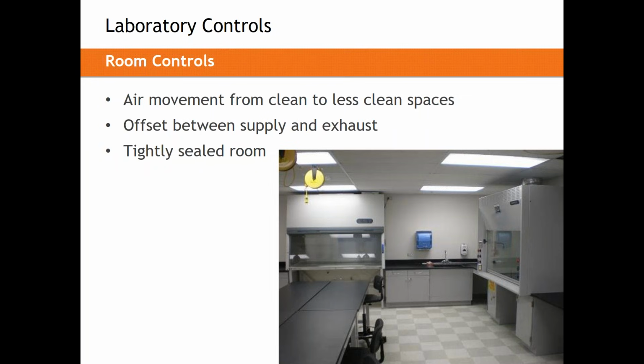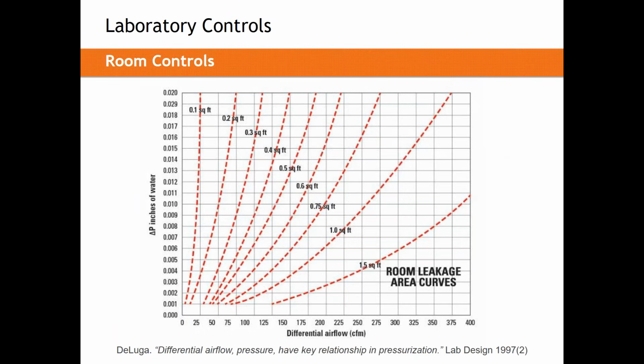And I say this because you're never going to have a perfect understanding of how tightly sealed your room is. You can get a general idea of room leakage. If you go into an old building on an old campus that's been leaky for 100 years, you know you're going to need a larger offset than a tightly sealed, brand new constructed high containment lab. But you won't generally know exactly how much leakage you have. So you could look at data like we have here, which is third-party data from '97, that lines up the open square footage you have versus how much airflow you need to achieve a certain pressure. For example, if you need 0.01, you know you have a half a square foot of open area, you'll need about 100 to 125 CFM of offset to achieve that.